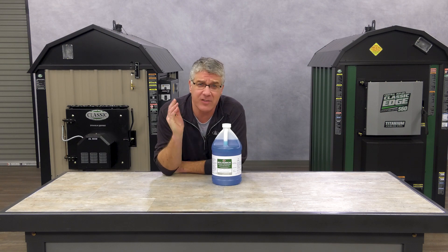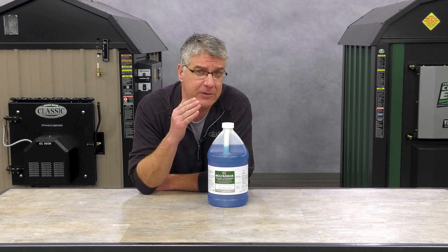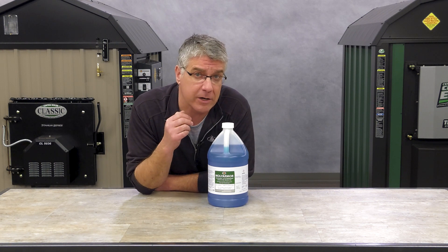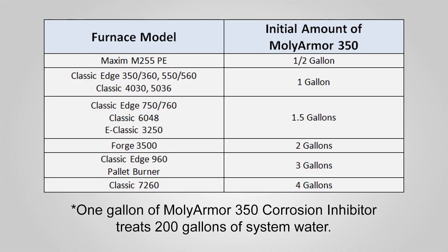Treating your furnace water is simple. Add the proper amount of MolyArmor 350 through the top of the furnace vent tube before adding water. We have a handy chart here showing how many gallons of treatment your furnace model typically needs. One gallon of MolyArmor 350 corrosion inhibitor treats 200 gallons of system water.